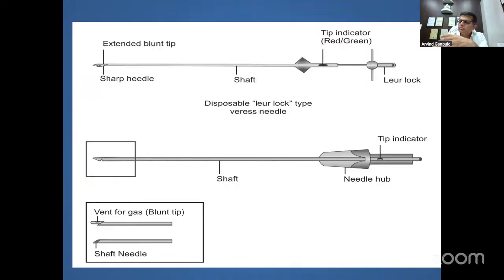Somebody might say that I'm wasting time on unnecessary things, but this is very important because we Indians are very cost conscious, and we tend to use instruments which are not intended to be reused. I have nothing against reuse, but if you want to reuse the instrument, always make sure that the vent is laterally directed. Sometimes if you reuse it, it is directed medially. Always see that the tip indicator is working, and that the hanging ball is moving. If the hanging ball is not moving, it might give fallacious results.